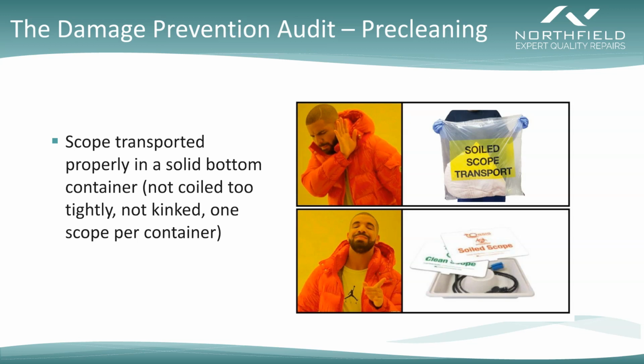So it's very easy in a compliance audit to miss that. Although this is okay in one sense, from a damage prevention sense, this is terrible. Every bit of weight of that scope is collapsing down on itself when it's transported like this. There's no support given to it, and this is absolutely what's going to cause the light guide connector to ram into the distal tip where that very sensitive bending rubber is. That's where your holes very frequently come from. And because it's wrapped up tightly with no support, that angulation system is getting stretched out like crazy.